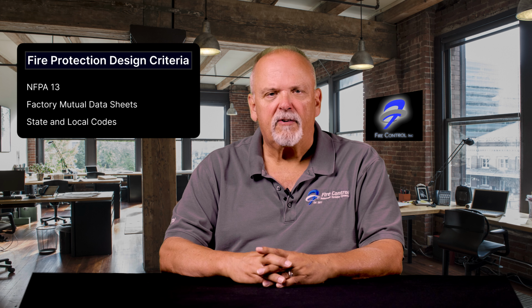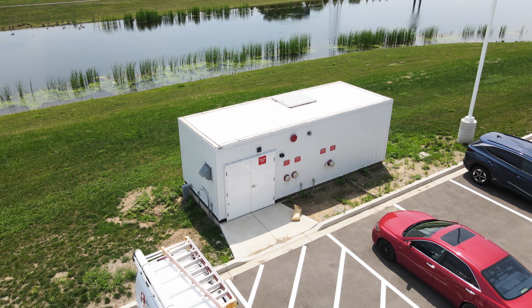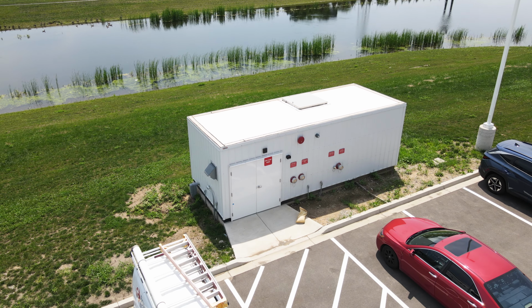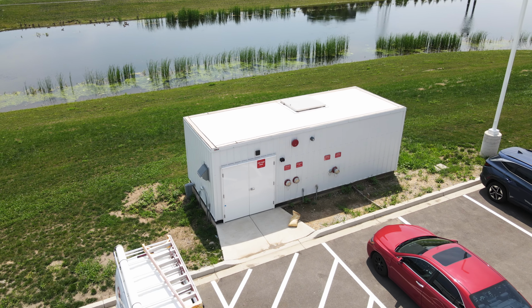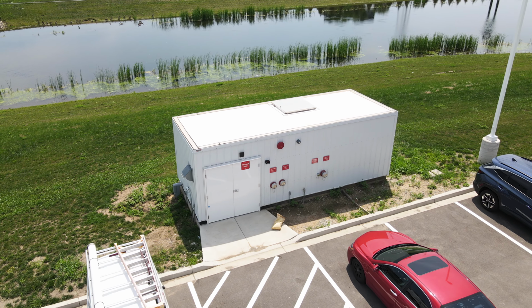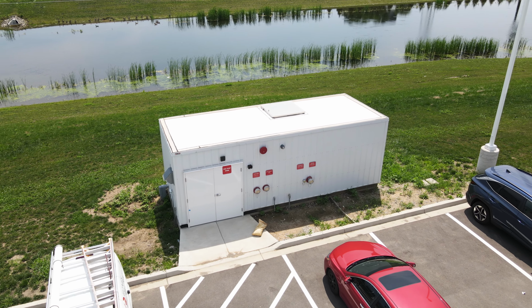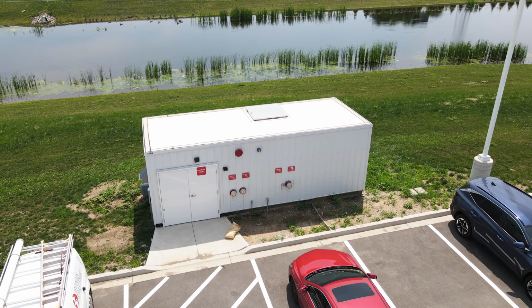This building is protected throughout with automatic fire sprinkler systems. These systems are designed and installed in accordance with NFPA 13, Factory Mutual data sheets, and all state and local codes and standards. The systems are supplied with water from the retention pond located immediately to the south of the building. Water from the pond is pumped with an electric vertical shaft fire pump located in the small building adjacent to the pond and accessible at the parking lot level. Inside this building you will find the fire pump and controller, jockey pump and controller, and other valves and support equipment.